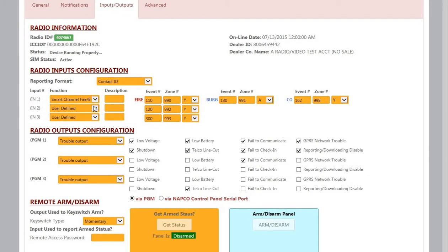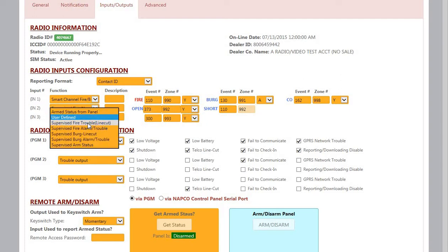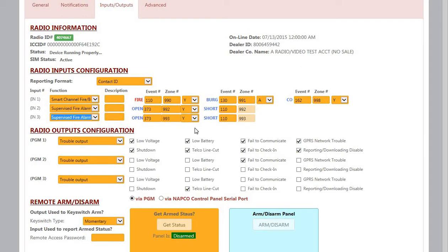Next, we're going to click on the inputs and outputs tab. We're going to set input number 2 for supervised fire alarm/trouble. And as you can see, a short will send a fire alarm, an open will send the trouble.